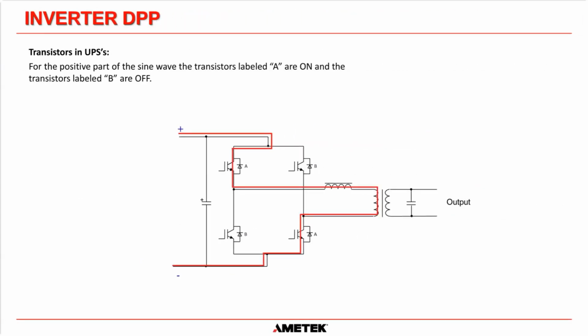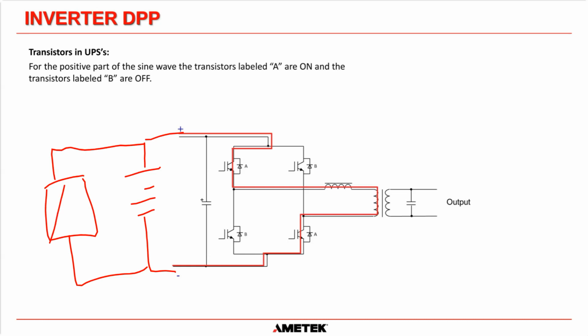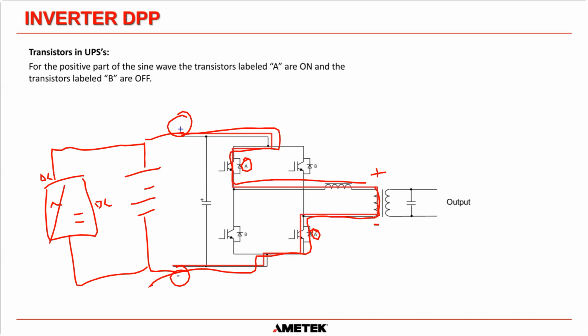On the left-hand side, you have your battery connected here, and connected to your battery back here, you have some form of charger. So you have AC to DC coming in here. That charges your batteries and also supplies power to the inverter, and you have positive here and negative here. What we do is switch the IGBTs on in pairs. So we are switching A and A on here, and you can see that the power flow is down through that one there. That makes this side of the transformer positive, and we get to the negative down through this one here, so we make that negative. If we were just going to send a square wave to this, that would give you the positive half of the square wave. There's a 0 volt line there.